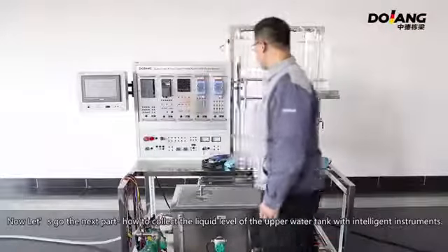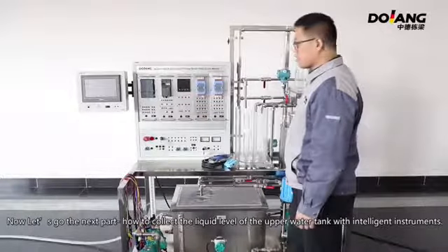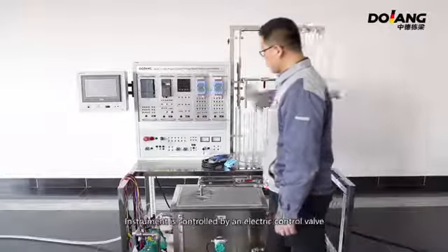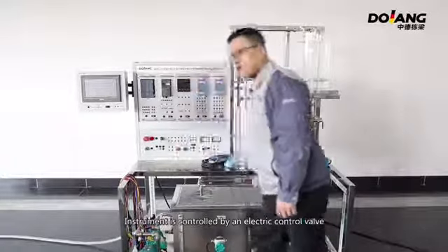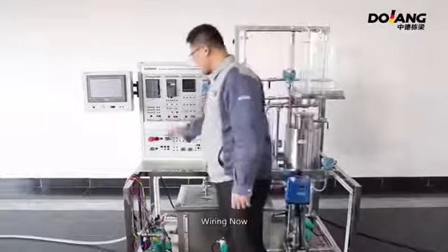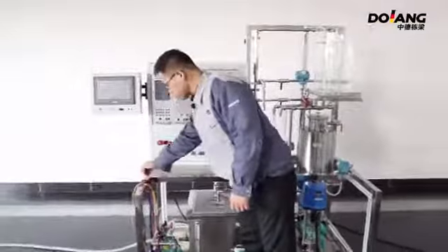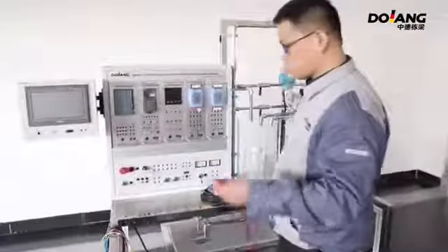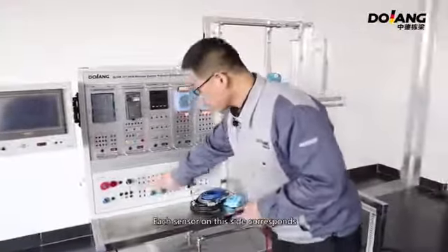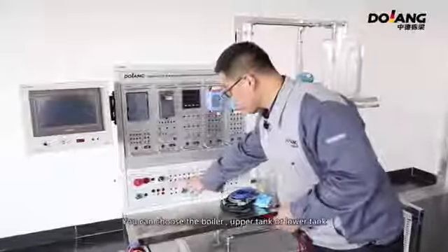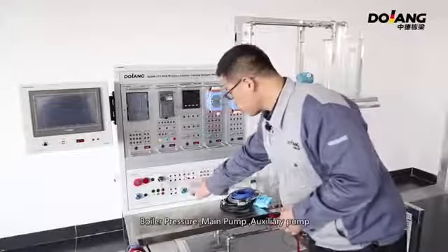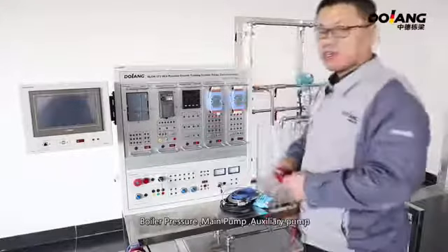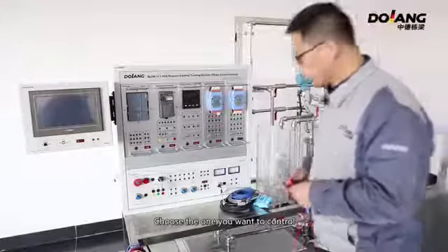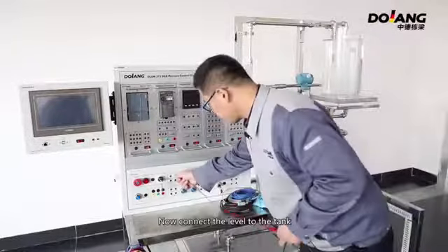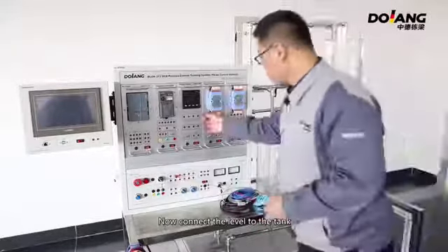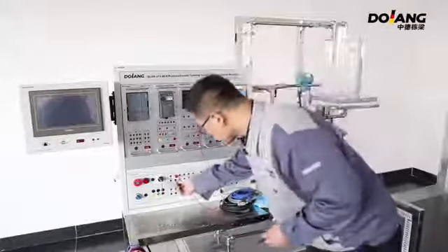level in the upper water tank with intelligent instruments. The instrument is controlled by an electric control valve. Wiring now. Each sensor on the side corresponds. You can choose the boiler upper tank or lower tank. Boiler pressure, main pump, auxiliary pump. Choose the one you want to control. Now connect the level to the tank.